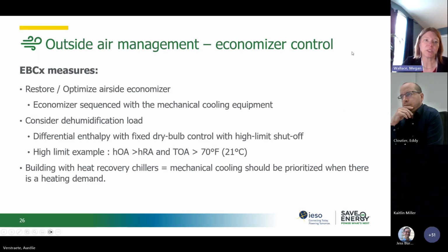So some of the EBCx measures we do related to economizer control. We will restore or optimize the airside economizer. So we'll make sure that the economizer is sequenced with the mechanical equipment. You'll have to consider the dehumidification load as well. We'll look at the differential enthalpy with a fixed dry bulb control with a high limit shutoff.